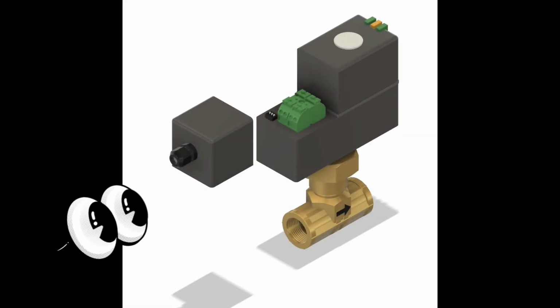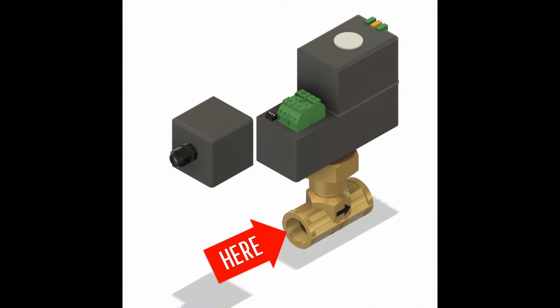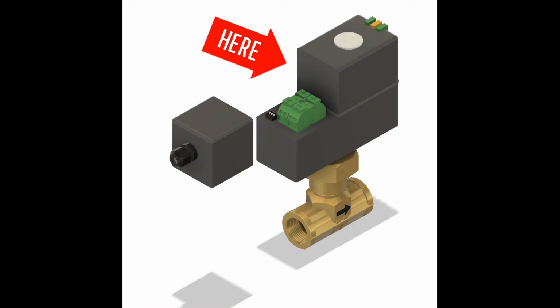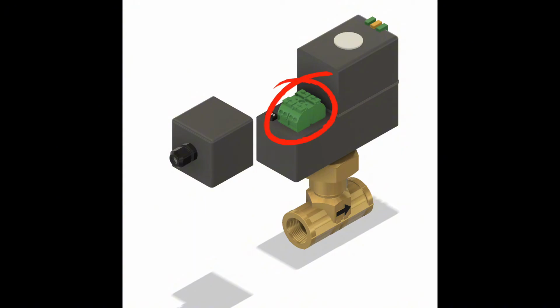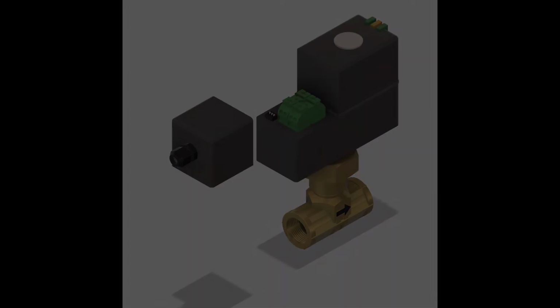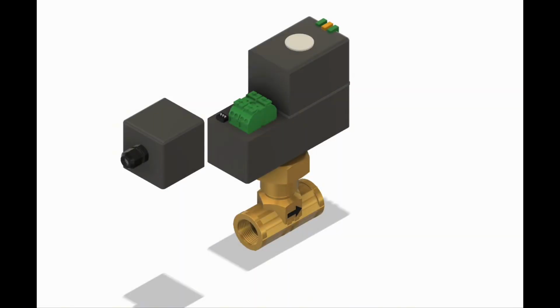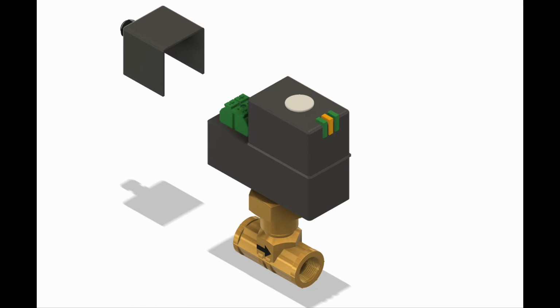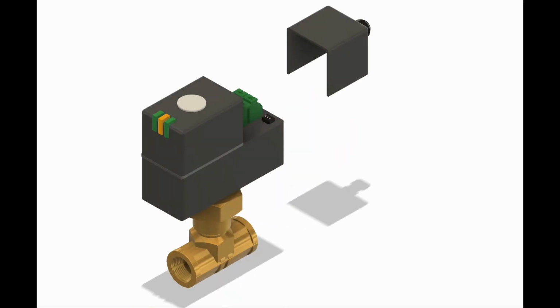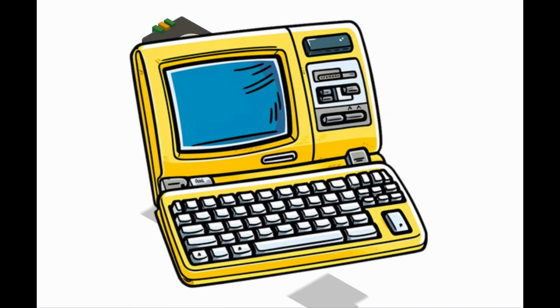So let's look at the main components of a PIC valve. You have the valve body, in this case 3/4 inch NPT. You have the electronic actuator that sits on top of the valve body. Something to note, these are one way. You see the arrow. Inside the actuator, there's the terminals where the wires land and some dip switches. You'll also see there's LED status indicator lights telling you if the valve is opened or closed on the other side here. These also can be manually activated, and they're controlled by your BAS system.